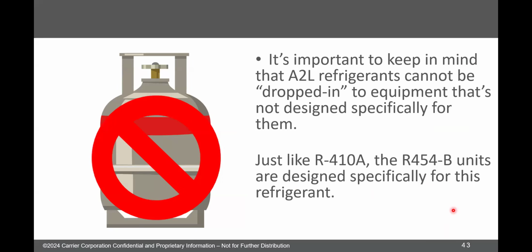And then no matter what you've heard people say, R-454B and R-32 are not drop-in refrigerants. You can't take them and put them into an R-22 and R-410A system. I mean, you could do that, but like it wouldn't be safe. It wouldn't be allowed. There's actually no reason to do it because you can't even get R-454B in any large quantity, right? So, but it's not a drop-in replacement.